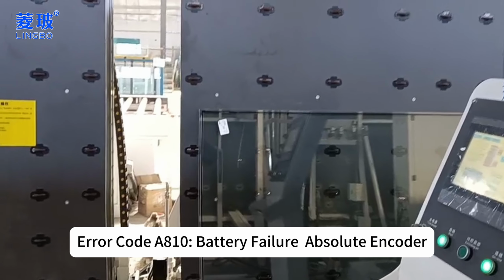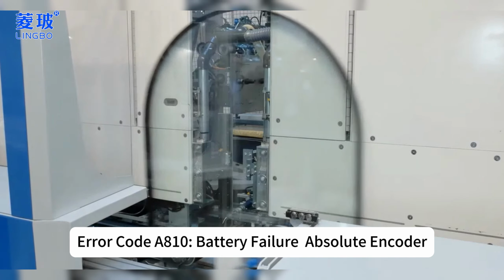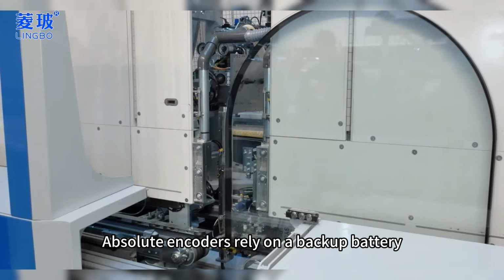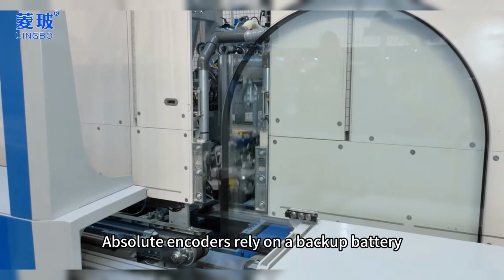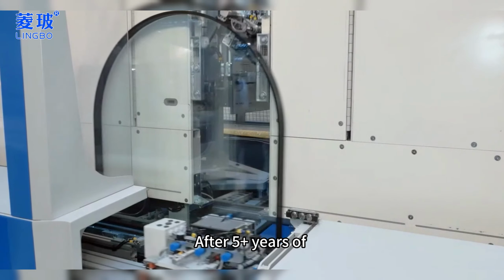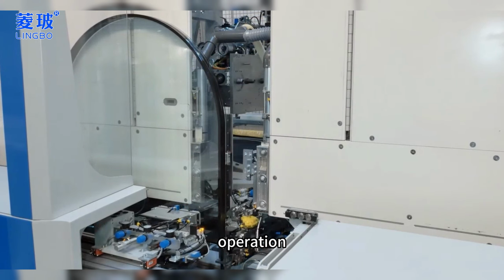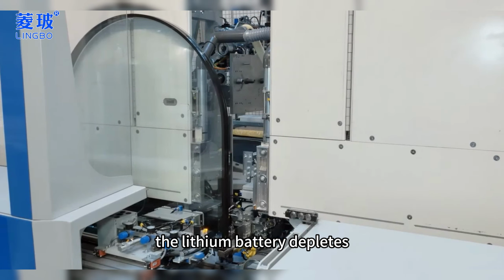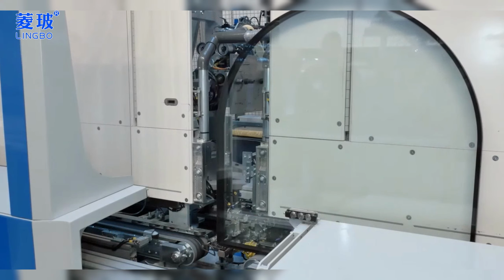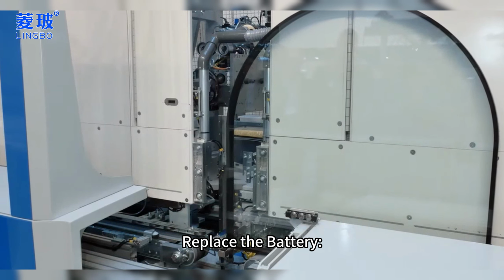Error code A810. Battery failure, absolute encoder. Root cause. Absolute encoders rely on a backup battery to retain position data. After 5+ years of operation, the lithium battery depletes, causing position memory loss. Solutions. Replace the battery.